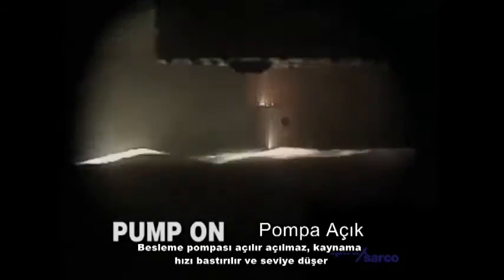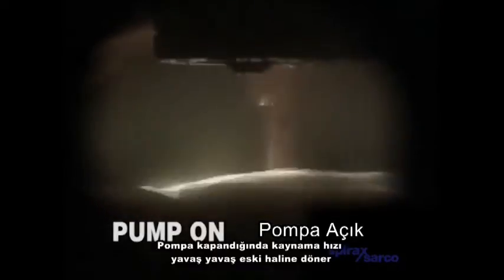Time-lapse photography provides a clearer picture of events. As soon as the feed pump switches on, the boiling rate becomes suppressed and the level falls. When the pump switches off, the boiling rate slowly recovers and the level continues to rise above the pump-off position due to the reappearance of normal steam bubbles. Notice how a mist forms just after the feed pump switches on. This is because steam is recondensing in the steam space due to the sudden lowering of the water temperature. The mist disappears soon after the feed pump switches off as the temperature begins to rise.